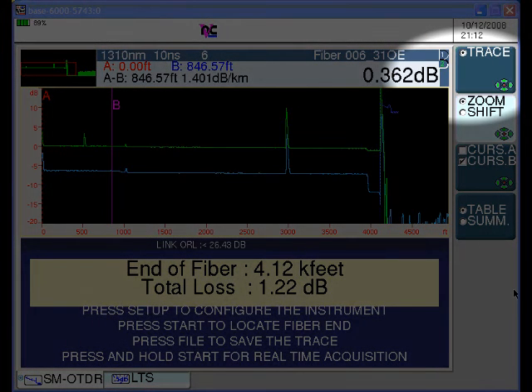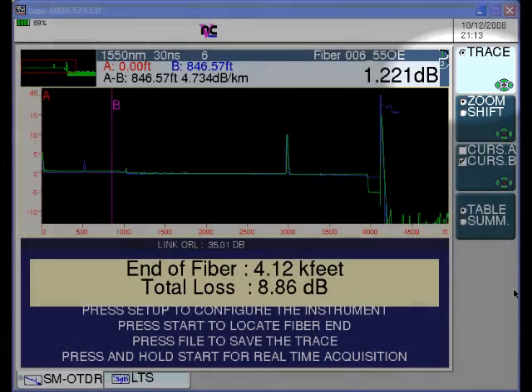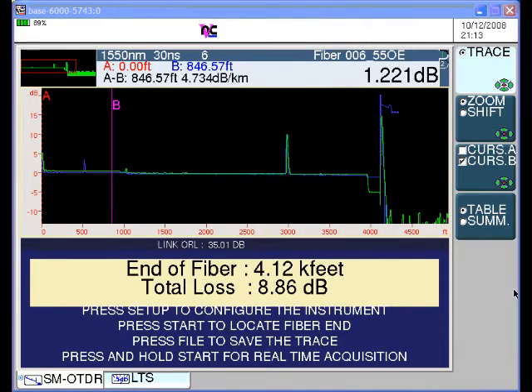We can press the trace button to switch from the 1310 nanometer display to the 1550 nanometer display. Here we can see that the end of fiber is located at the same position, 4,120 feet, but the end-to-end loss is almost 9 dB, or 8.86 dB. The 1.221 dB shown at the top of the screen is the loss between the A and B cursor and does not necessarily represent the total loss of the span. Looking at the screen at about 4,000 feet, we can see that the active trace — the green trace at 1550 nanometers — has a very large loss event just before the end of the fiber.